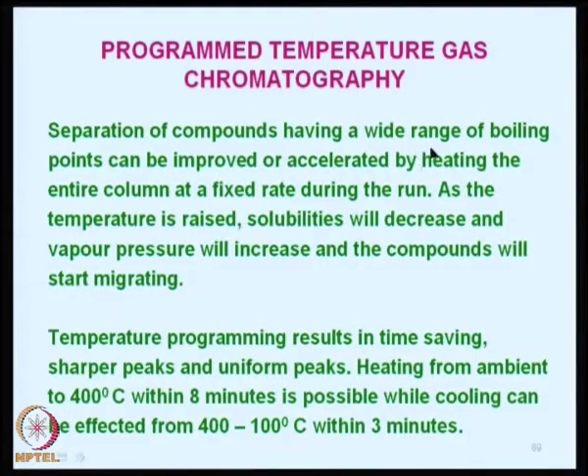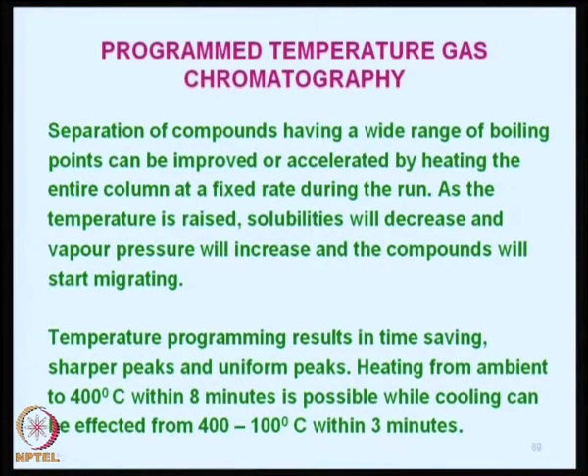The wide range of boiling points can be improved or accelerated by heating the entire column at a fixed rate during the run. As temperature is raised, solubility decreases and vapor pressure increases, causing compounds to start migrating. Temperature programming results in time saving, sharper peaks, and uniform peaks. Heating from ambient to 400 degrees centigrade within 8 minutes is possible, while cooling from 400 to 100 degrees centigrade can be effected within 2 to 3 minutes.